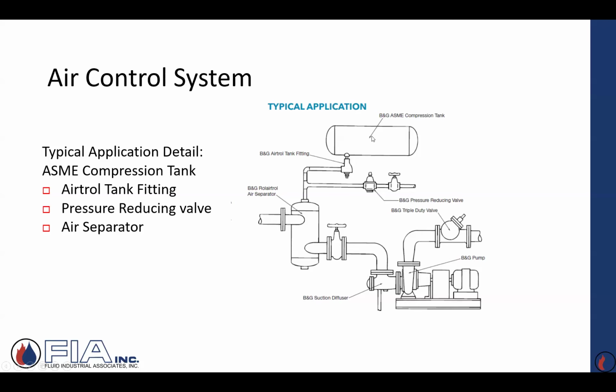Well, how could you establish that? So what they would do is they would use this Airtrol tank fitting that had a tube inside here. And it was a tube within a tube. And as you filled the system, you had the vent at the bottom open. And as the water's coming in, it's displacing the air out this vent. When water would suddenly start kind of dribbling out the bottom vent here, the guy would close it. And now we had the right ratio of air to water in the tank.